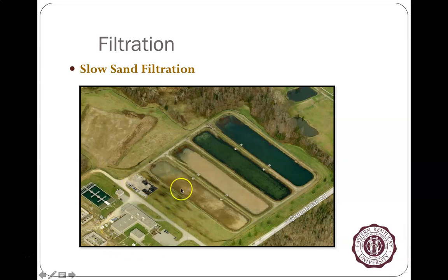This one is recently offline. This one is ready to be used, and these are actively being used. Water in slow sand filtration is being sent from the sedimentation basin to the slow sand filter, and over time the water will work its way through the sand and go to an underground storage well, where it'll then be ready for disinfection.